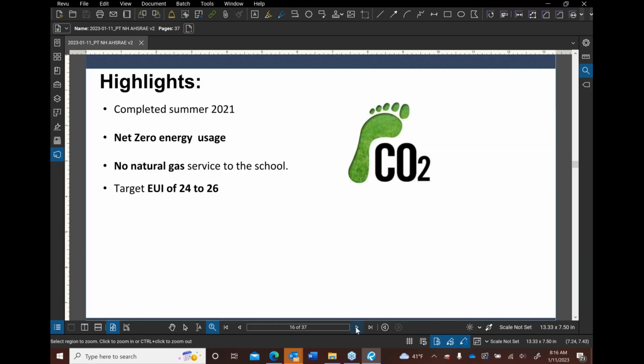It was completed in the summer of 2021 and opened for the start of school in August 2021. It is net zero energy, kind of unofficially net zero. We just completed our first year of monitoring, and now we have to go through the verification process. There's no natural gas service to the school, and our target EUI was 24 to 26. You'll see what our actual EUI was a little later.